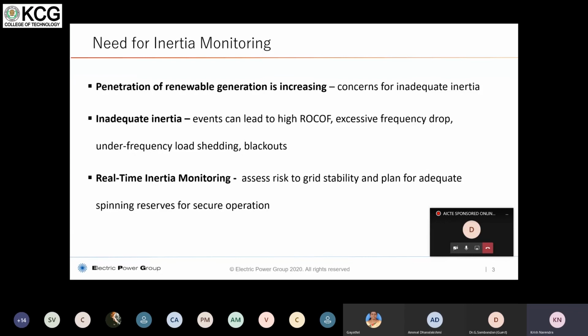For example, if you take away 1000 megawatts suddenly from a tie line that is flowing, then if the topology of the power flow is stable, the system can sustain it. In most cases, changes of hundreds of megawatts are not a big deal in a big synchronous grid, but thousands of megawatts is definitely a big deal if you take them off suddenly. So it may lead to blackouts and other things. There are cases that have happened in the practical world, and therefore it is very important to estimate the inertia as closely as possible in real time or near real time, to make sure of the stable operation of the grid and that enough spinning reserves are available to secure your operations.